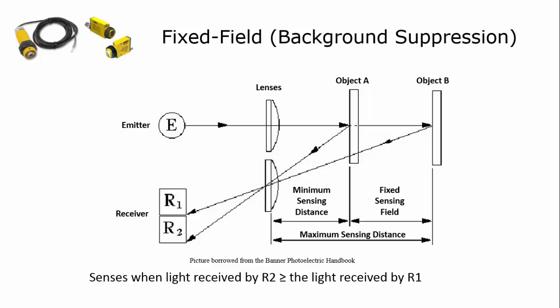This is a depiction of a fixed field background suppression sensor. You have the emitter over here emitting light. They are lensed. You have R1 and R2, so there's two receivers. Light comes off and reflects off of this object, which is called object A, which is actually the first position of the object. The light comes off, reflects, gets collected by the lens, and you can see here that it's striking R2.